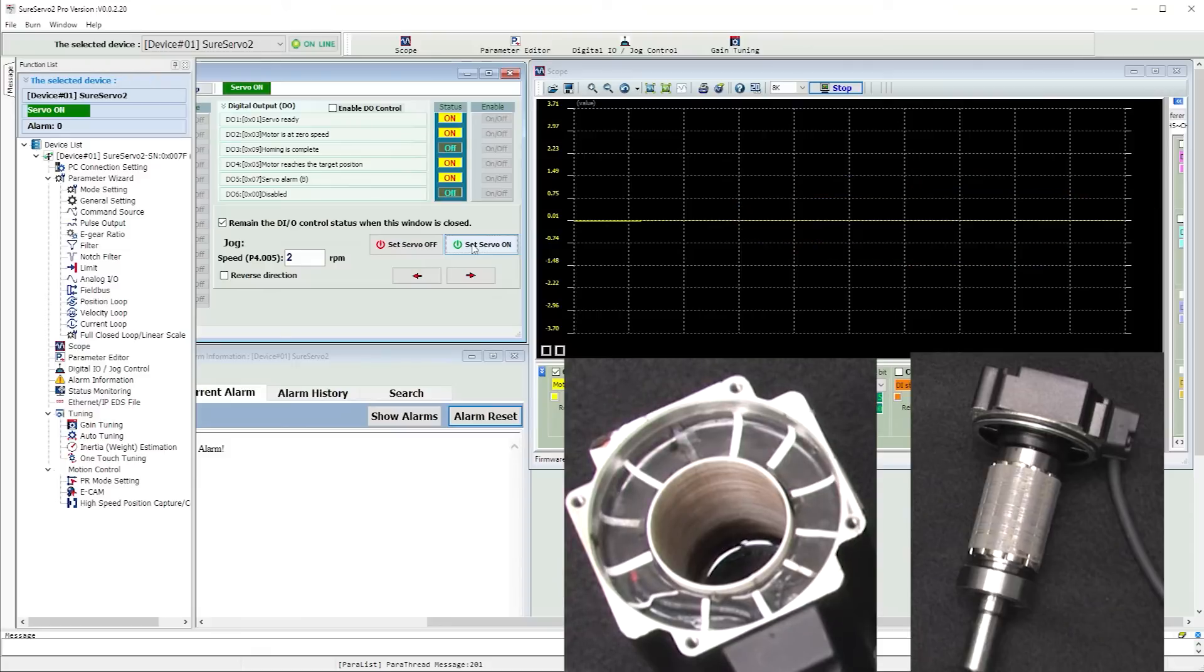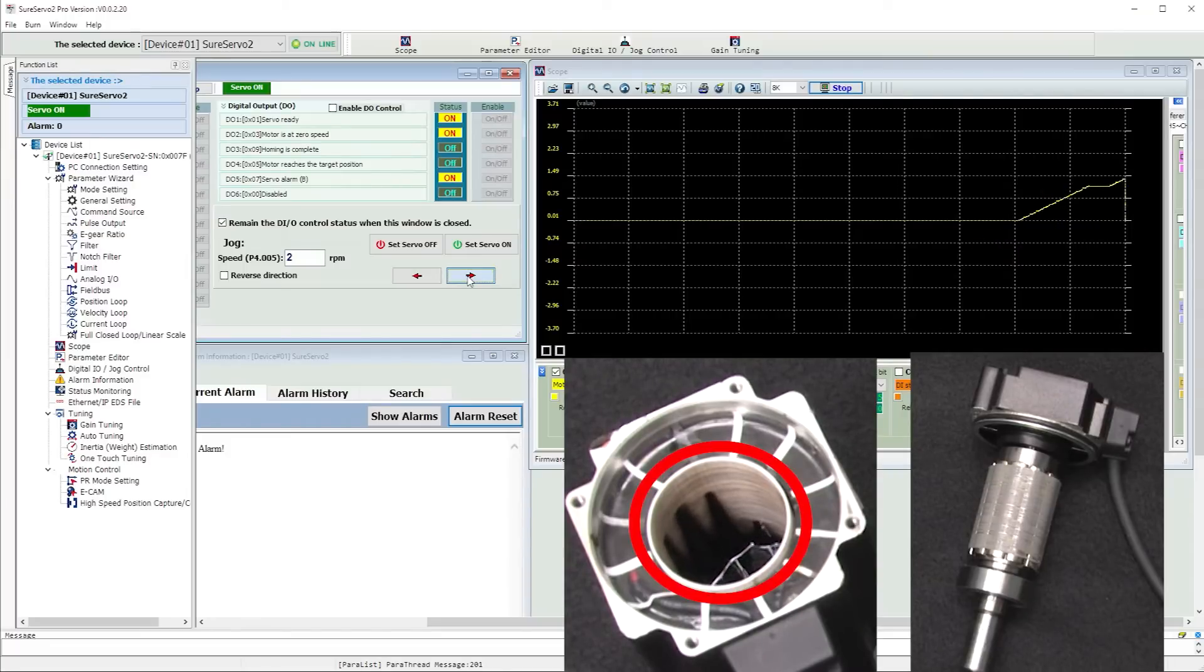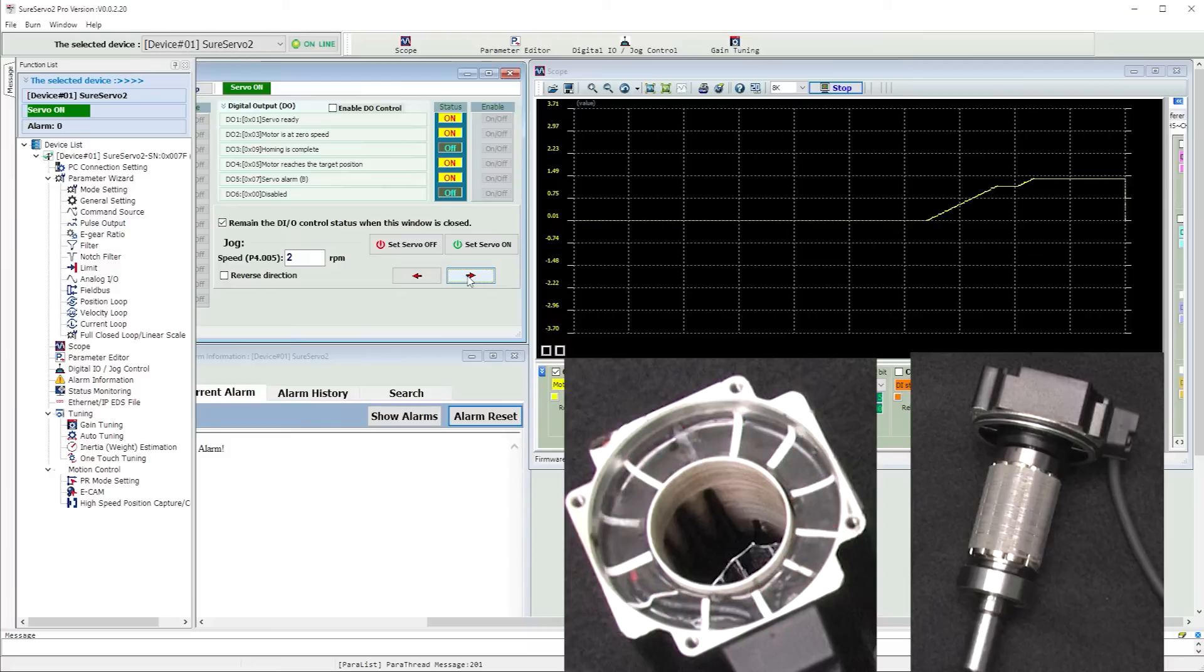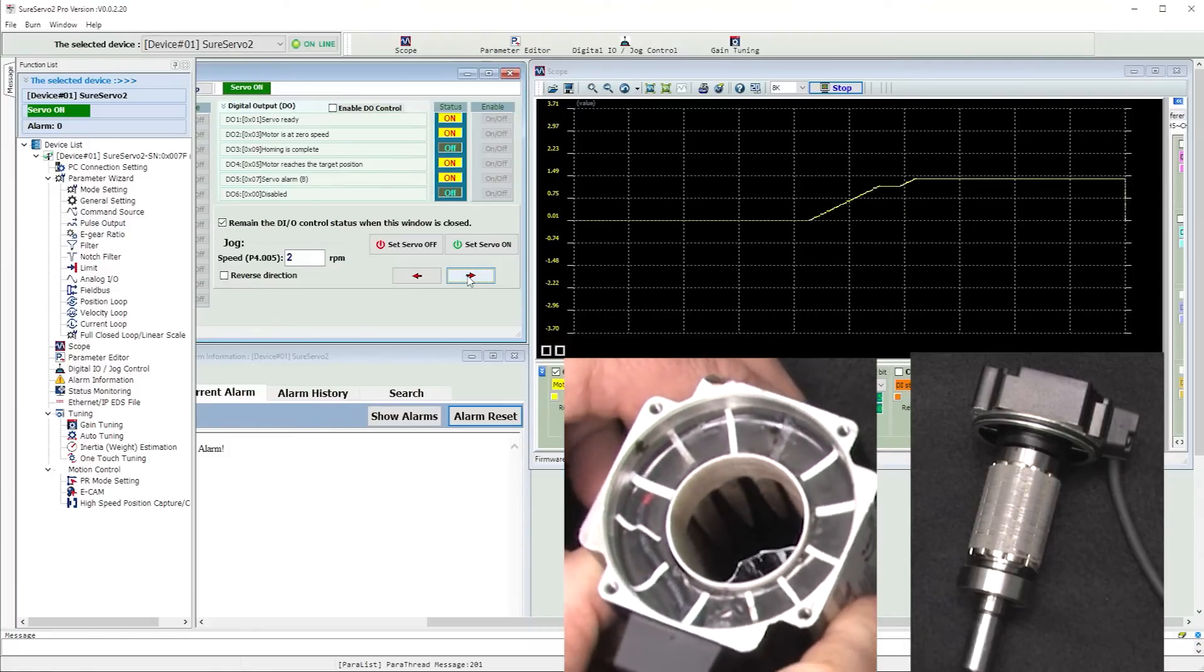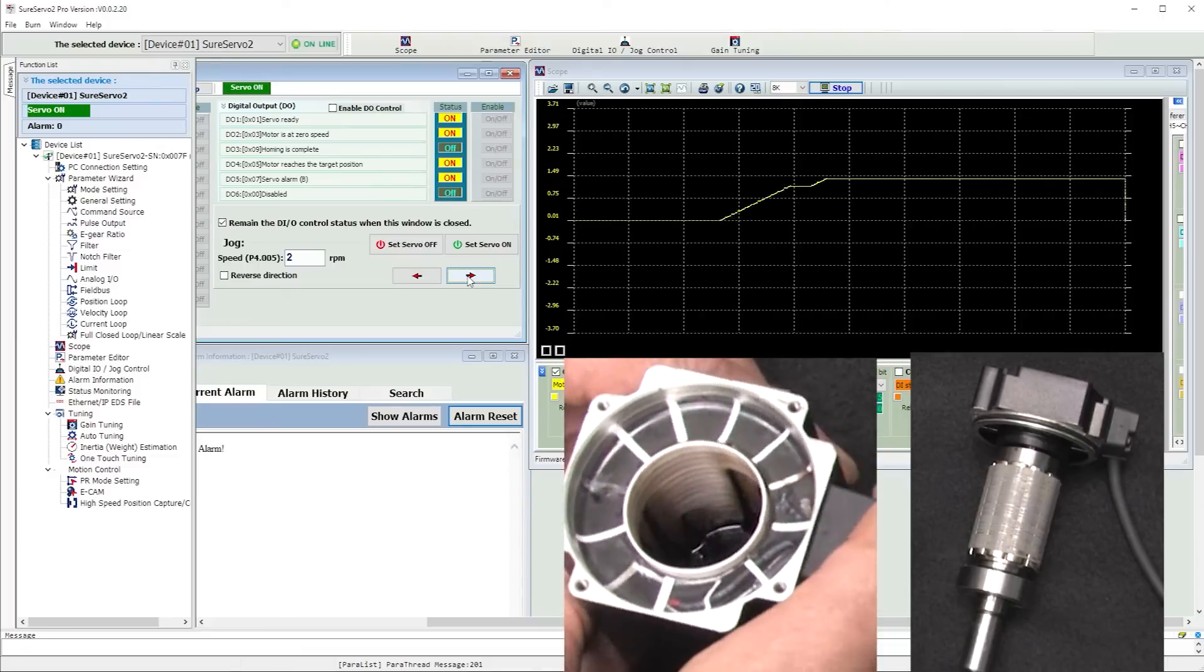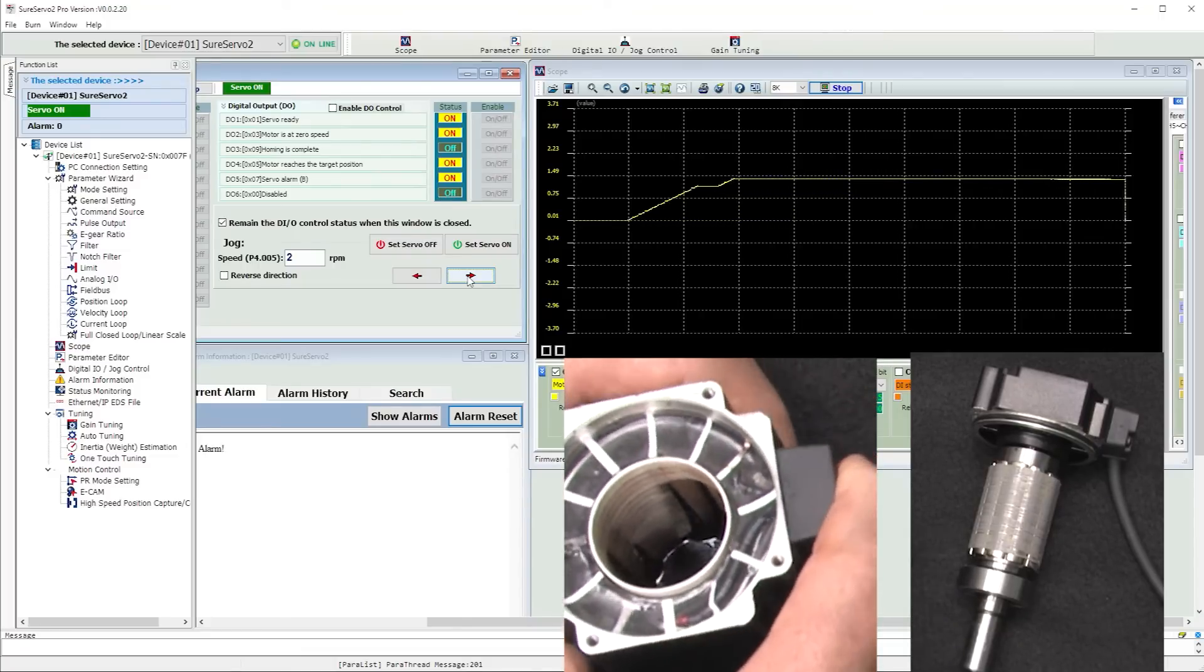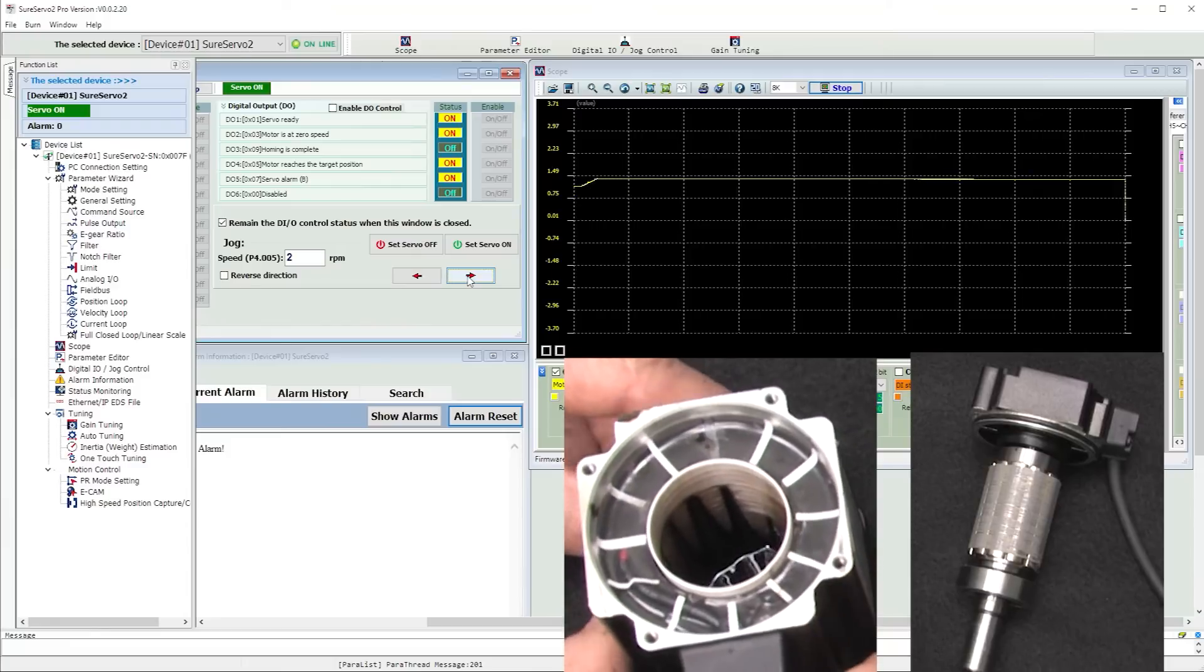If I tell the drive to move the rotor by pressing the jog button, then look what happens. The total motor current increases and the drive builds up a magnetic field in the stator to try and move the rotor which isn't actually there. And where is the magnetic field? Between the two windings, just like we saw with the rotor magnets. And look at the shape of the magnetic field. It looks kind of sinusoidal with the opposite pole mirroring the other one. Exactly what we expect to see.